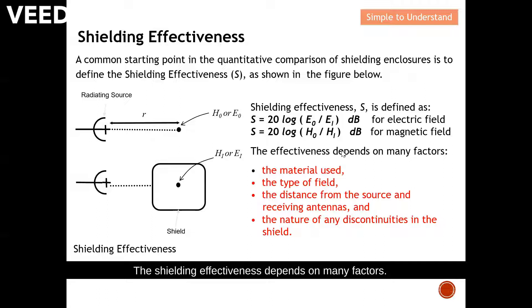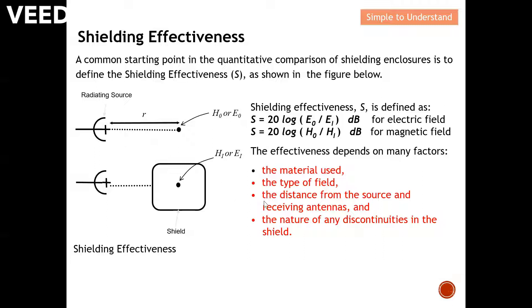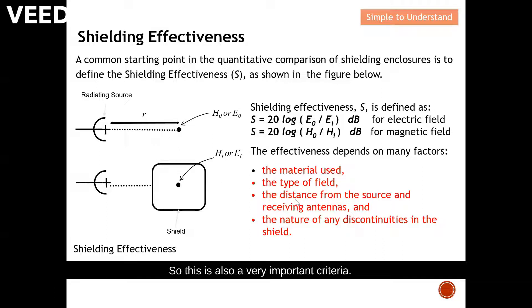The shielding effectiveness depends on many factors. First, the type of material you're going to use. The type of field, which means is it E field or H field. The distance from the source and receiving antenna—the further you are, most likely you're receiving a weaker signal. And the nature of any discontinuities in the shield, which determines the overall effect of the shielding.